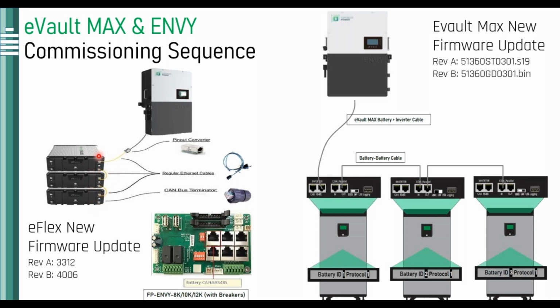You screw it in, then you connect the communication cable from battery to battery that's included also with your battery packaging. And then you're going to take the leftover battery cable and connect it to this pinout converter. This pinout converter is also another terminator to terminate the communication between battery to battery. But as you see, it's also a female coupling. So internally, it has a 120 ohm resistor that's going to terminate the communication, and then it's going to let through CAN communication and RS485. Out of both of those, it's going to go directly into the RS485 battery CAN port. Okay, so it's very important to use the equipment that we as a manufacturer provide you, not just another female to female coupling. You use these exact things.